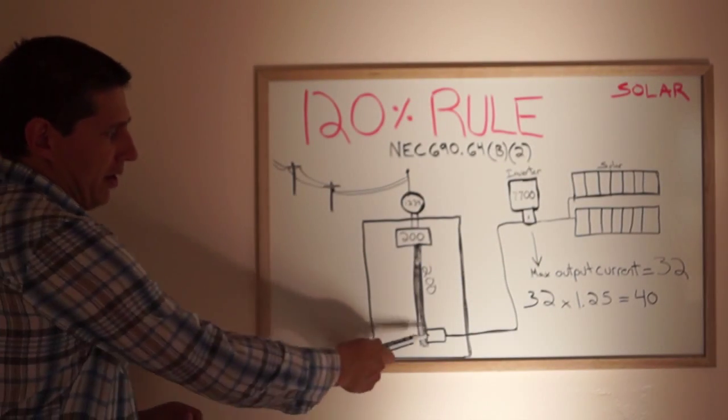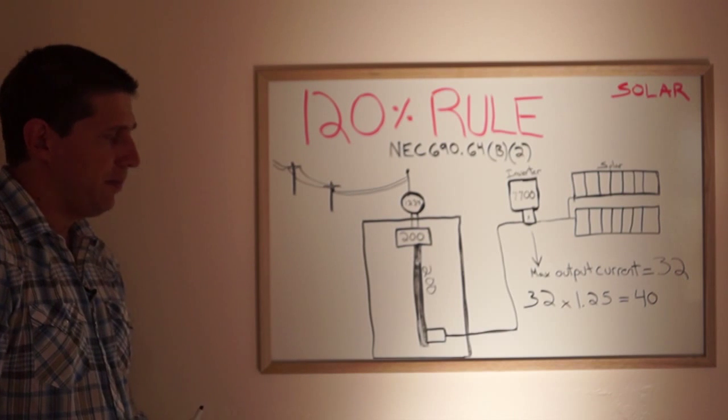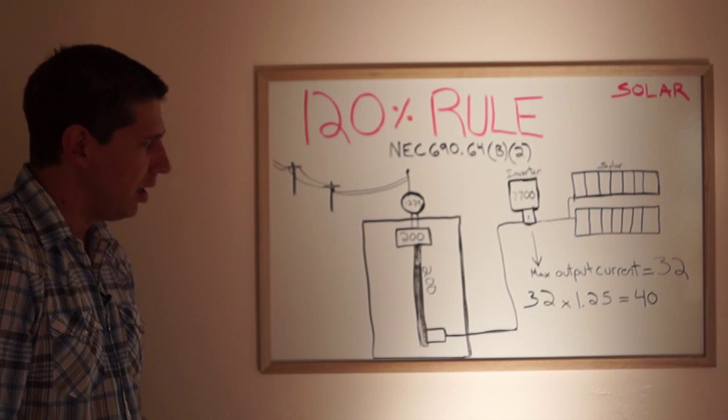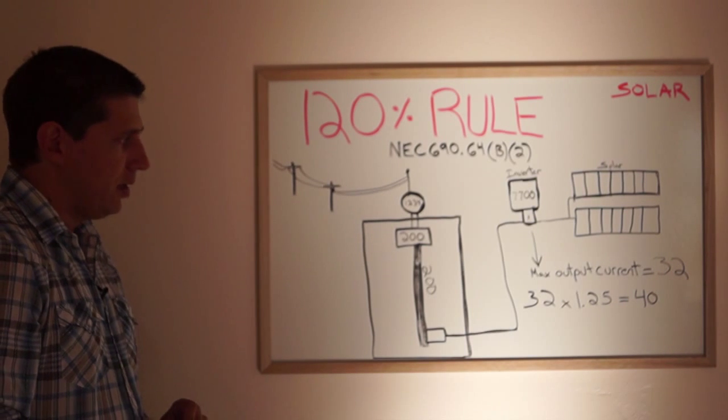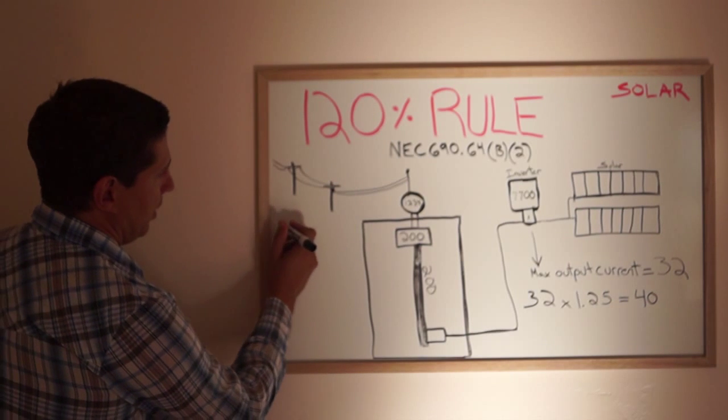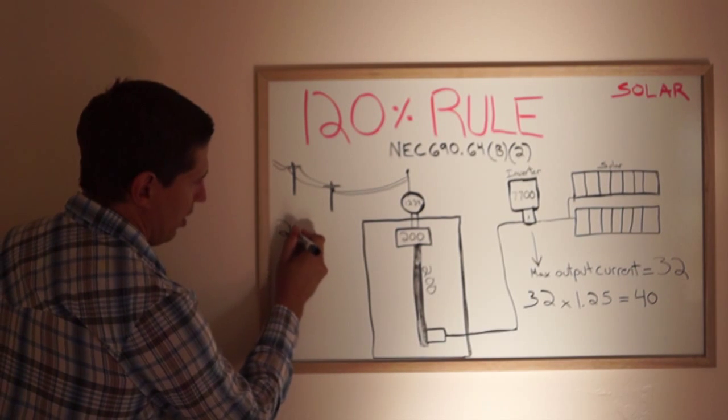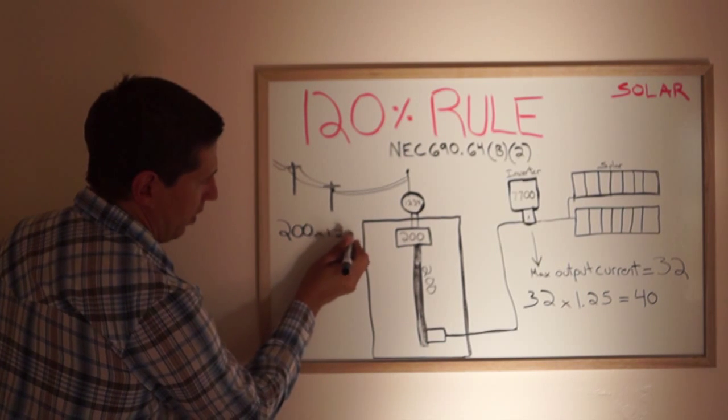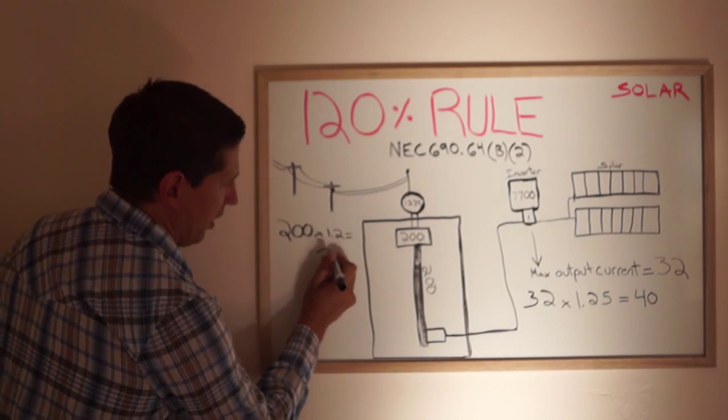So we have a breaker. And the 120% rule essentially limits how big of a solar system we can install. So what it is very simply is 200 times 1.2 equals 240.